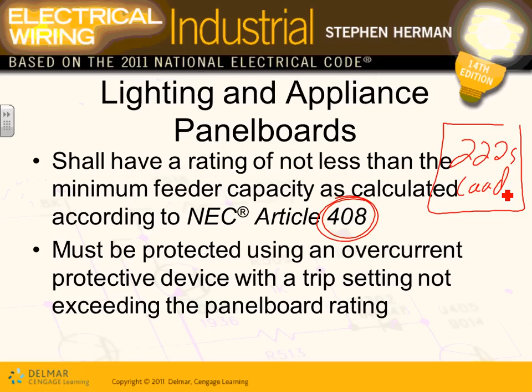And also you have to have an overcurrent protection device right in the panel, right here. So this has to be a 225 amp or less. So you have to protect the panel with an overcurrent protection device that's equal to the amp of the panel or less, not more. So Adam, for a 225 amp panel, I cannot put 300 amp to protect it. It has to be 225 amp or less than 225 amp.